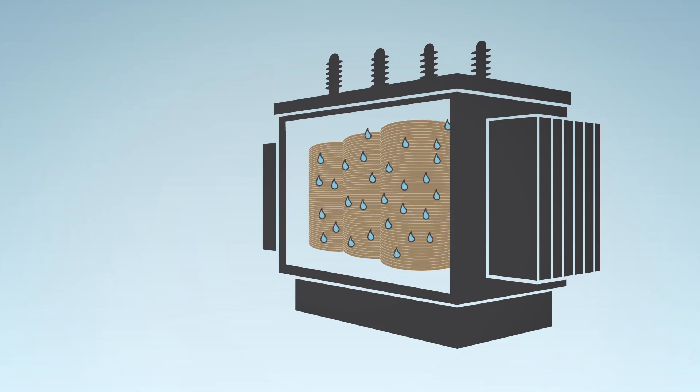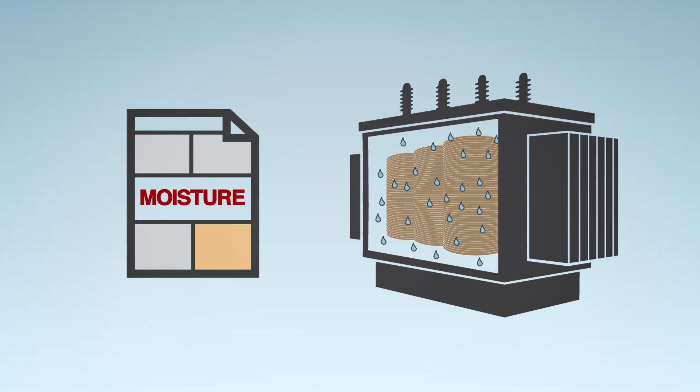So you dry the oil, but over time the moisture in the paper just seeps right back in. And before long, you have the same really high moisture levels again in your test results. This temporary solution is really no solution at all.